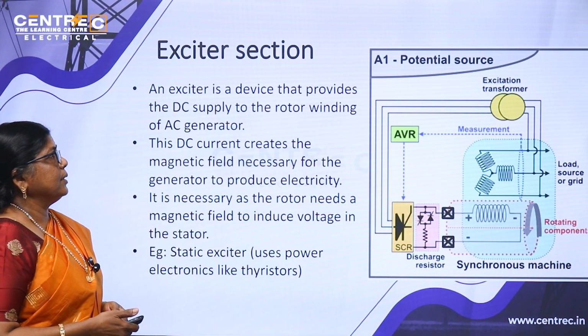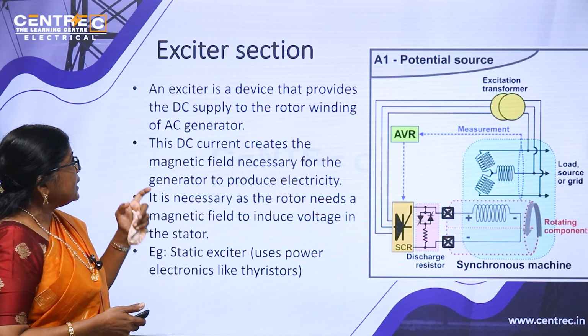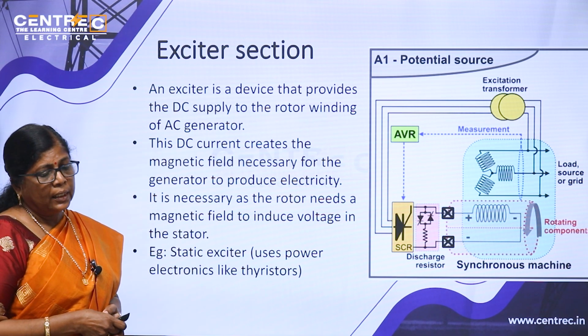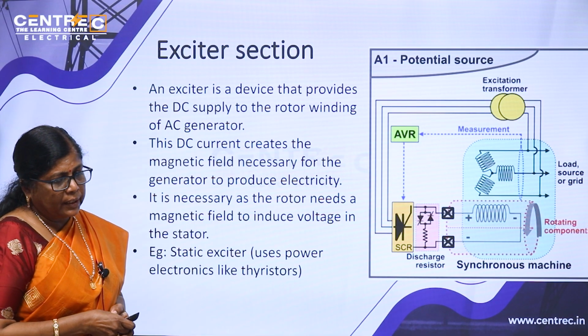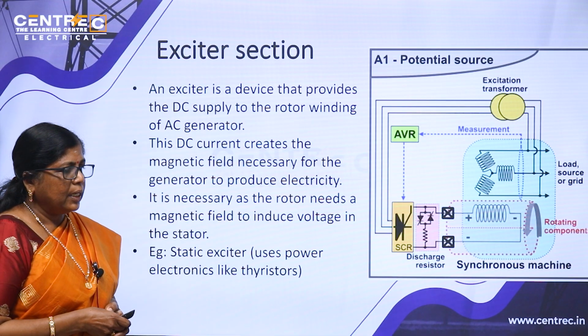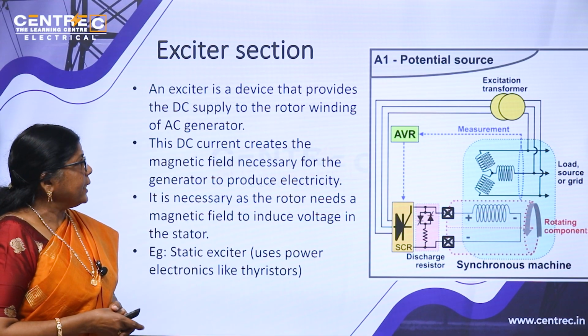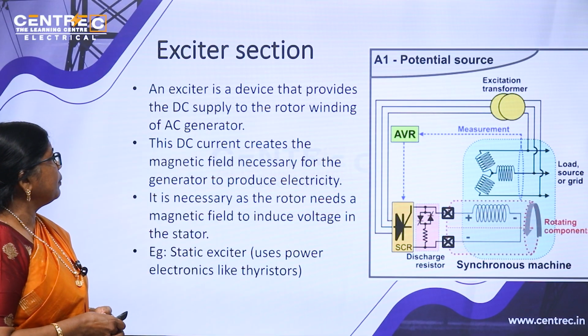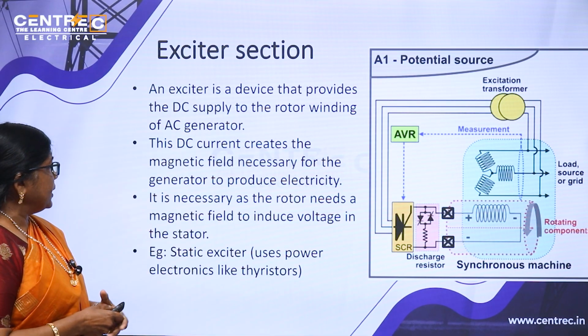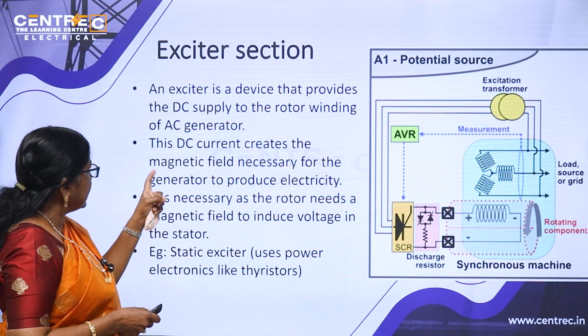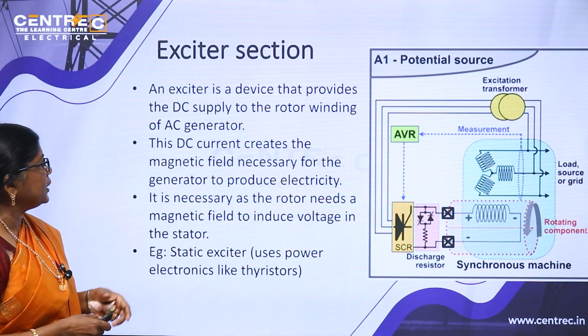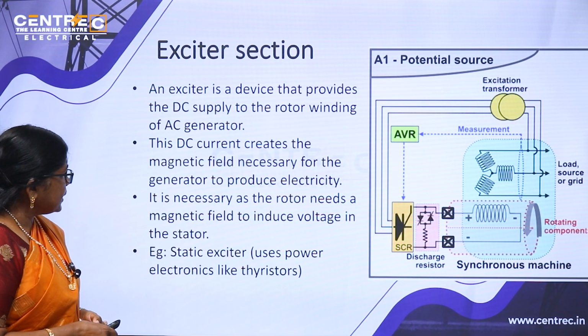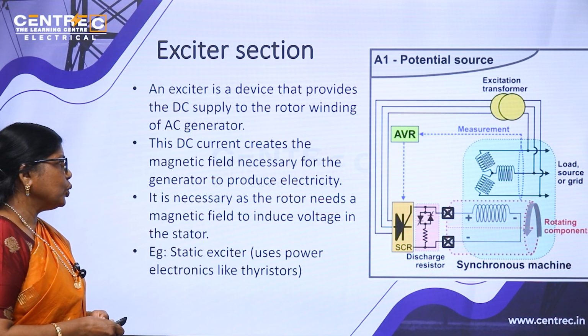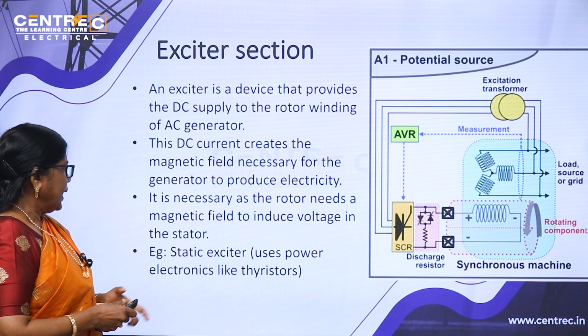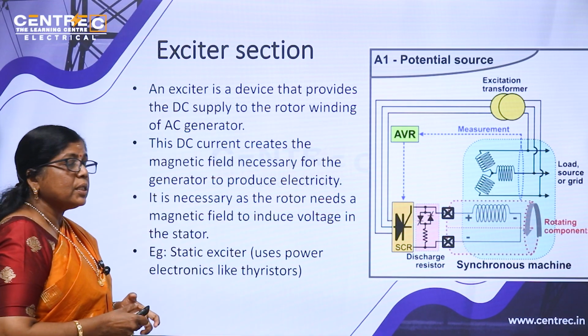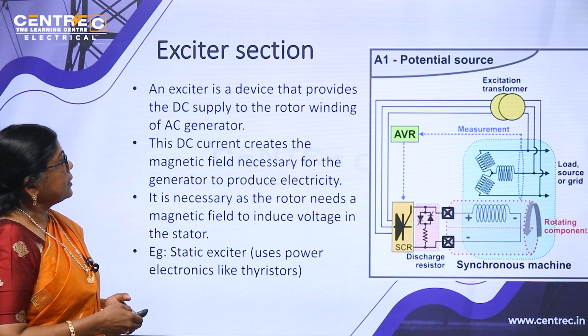Then the exciter section. The exciter provides DC supply to the rotor windings of the AC generator. Whenever there is a power station, we sometimes use electronic excitation or mechanical excitation. Here we can use DC supply by thyristors. This DC current creates the magnetic field necessary for the generator to produce electricity. It is necessary as the rotor needs a magnetic field to induce voltage in the stator. For example, a static exciter uses thyristors, SCRs.